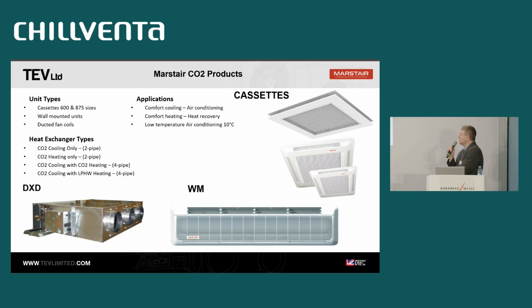We've also seen it where people will just want the CO2 cooling, but rather than running the hot gas through the store, they'll recover the heat into a plate heat exchanger and then run the heat through an LPHW. So we do basically the different types through the various areas. And like I say, it tends to be for comfort cooling, comfort heating on heat recovery. But we've also done some low temperature aircon as well, for food prep areas and that type of thing.